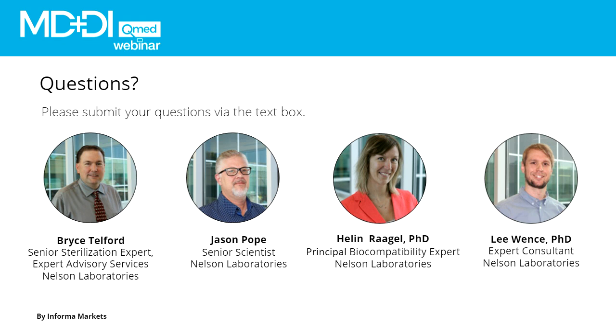So that's the whole thing. That's where we don't have that acceptance criteria for peroxide residues, and that's why we need to have all these conversations with the toxicologist to figure out what patients this is used in, so we know how to actually derive the values. How many devices are used? What patient weights are included? How long are the devices used? And then the toxicologist will search through the literature and write a document to establish the limits for that specific type of device.